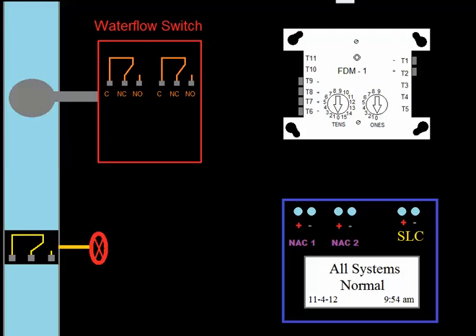I turn this screw on the 1's place to 1. Terminals 6 and 7 are automatically going to be address 1. And terminals 8 and 9 are going to take the next highest address in sequence. So terminals 8 and 9 would now be address 2 automatically. So the only thing I would set would be the first number, the lower number. Like I said, in this case I'm just going to pick address 1 even though the arrows aren't showing it. And let's say I do that.